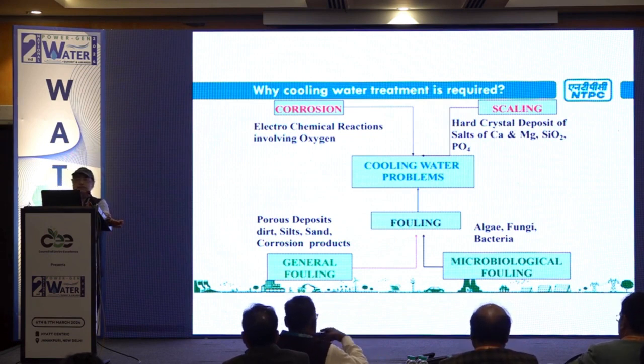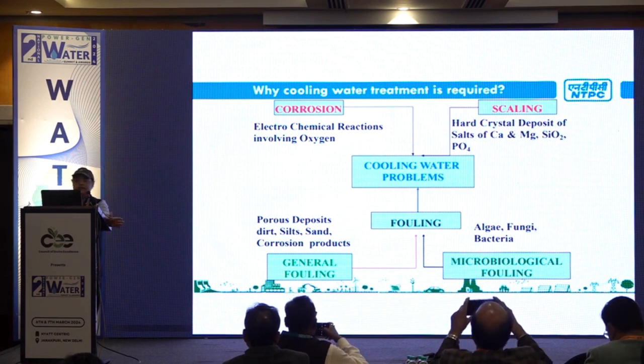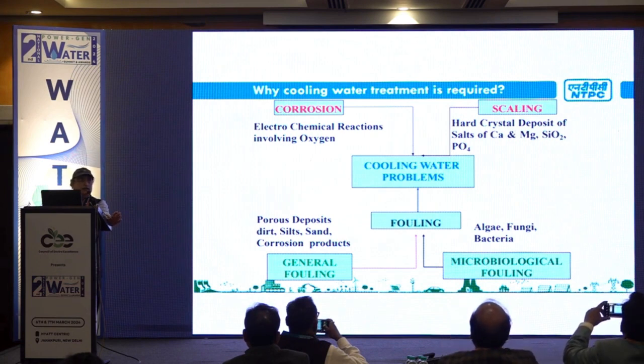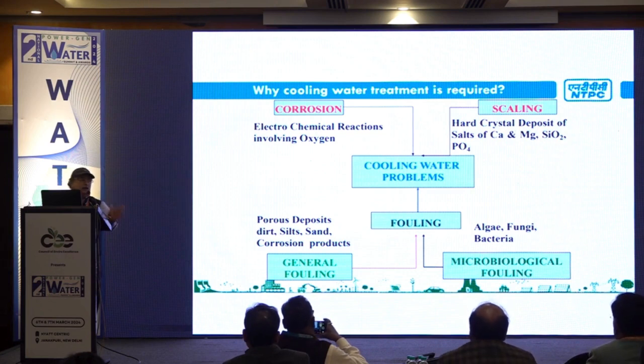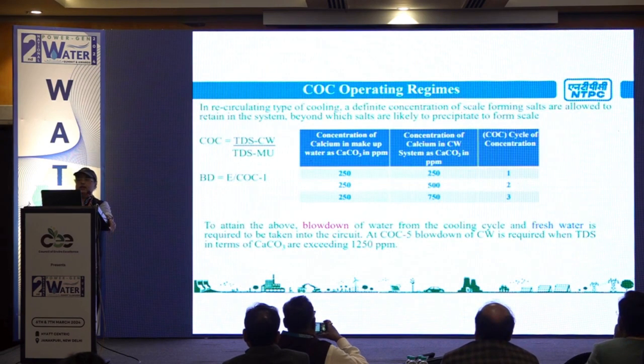Now I will confine mainly to cooling water treatments. That treatment is essential to manage our corrosion, scaling, fouling, etc. We have to use 4 or 5 chemicals that can arrest or control scaling, corrosion, or microbial fouling. Everyone knows what those chemicals are, but I am going to describe what we are actually using.